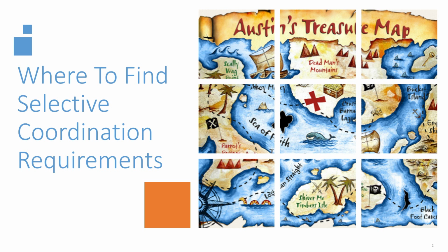I think it's very important that we understand that the mandatory selective coordination requirements are not in chapters 1 through 4. Okay, we're not going to find this anywhere in 210 on branch circuits. We're not going to see it in Article 215 for feeders. We're not going to see it in Article 240, because 1 through 4 is generally going to be all premises electrical installations and not going to include selective coordination.